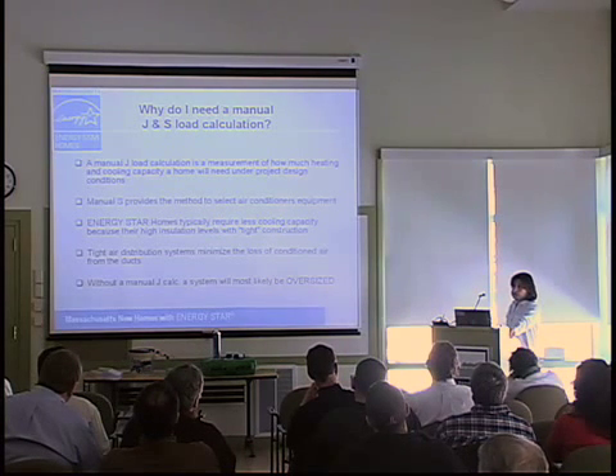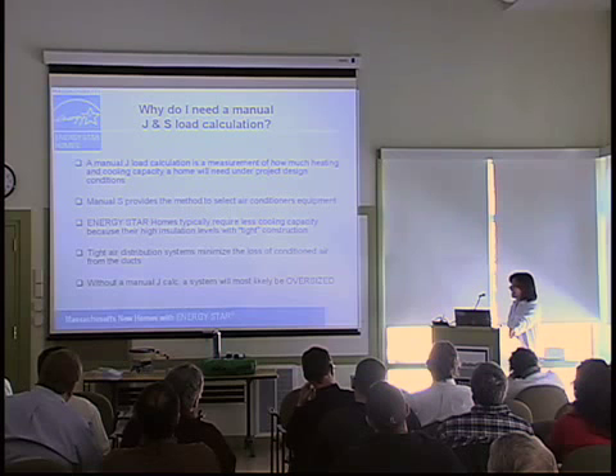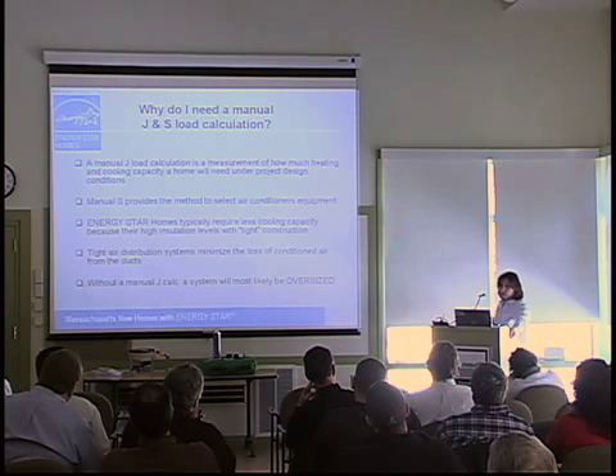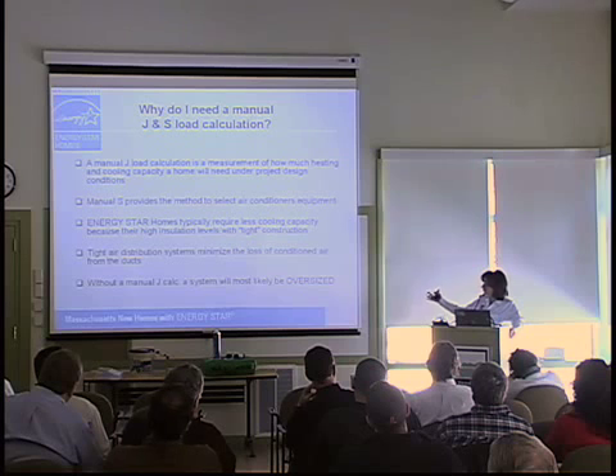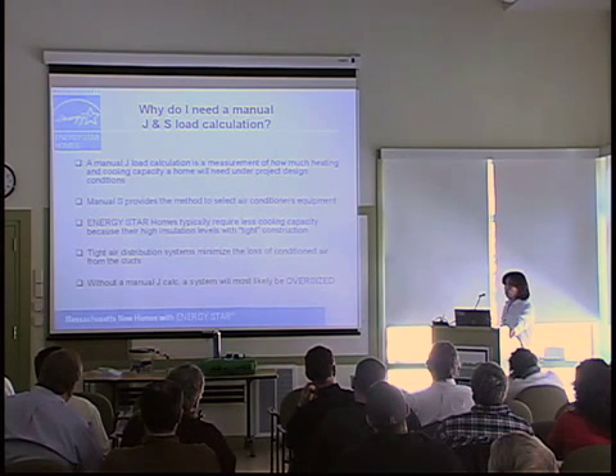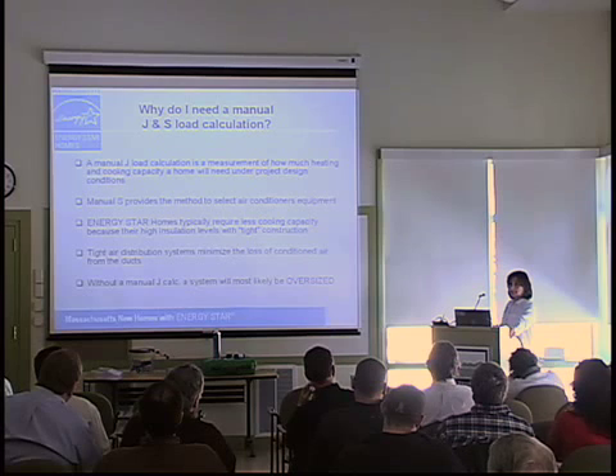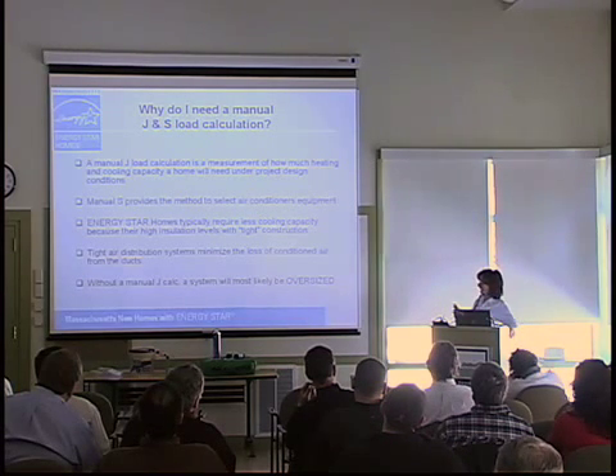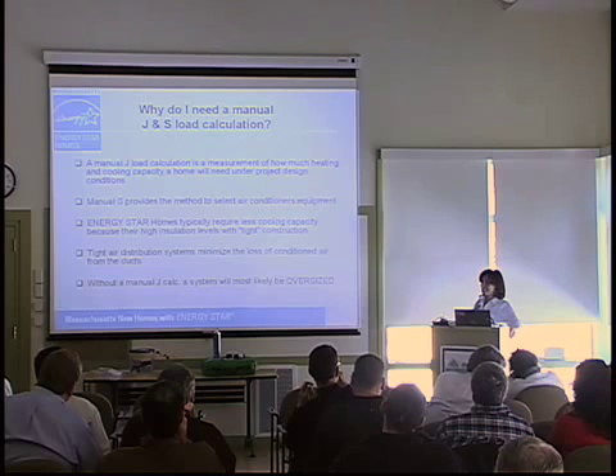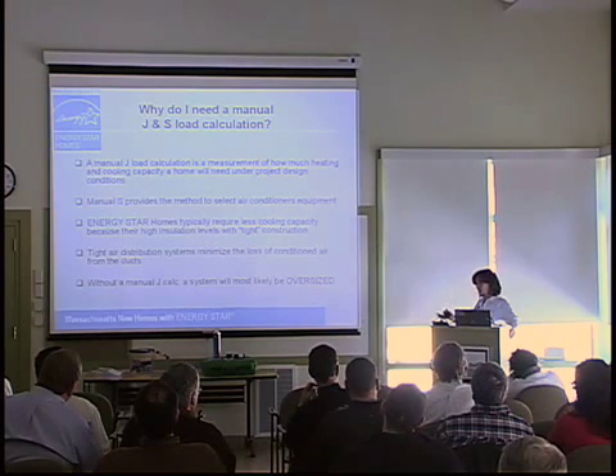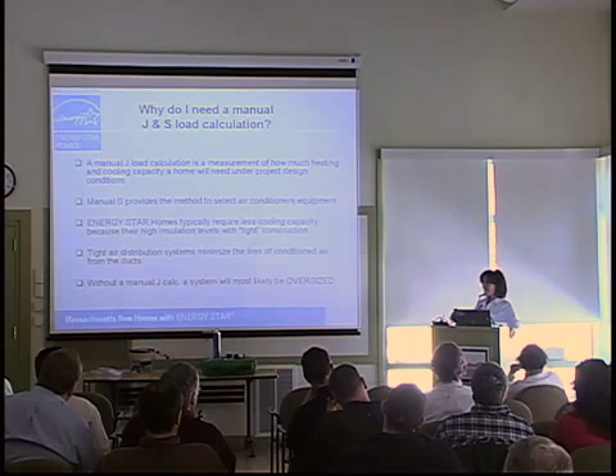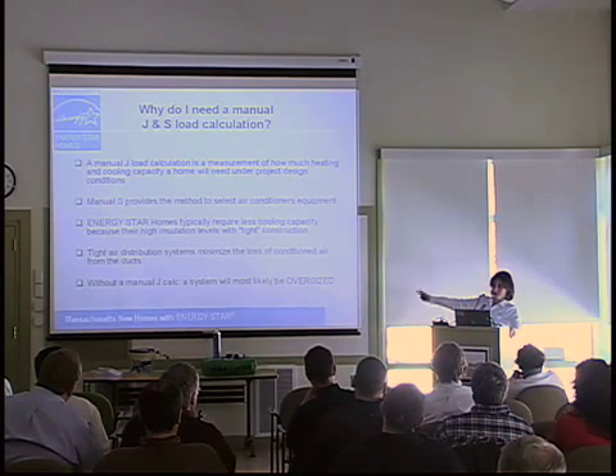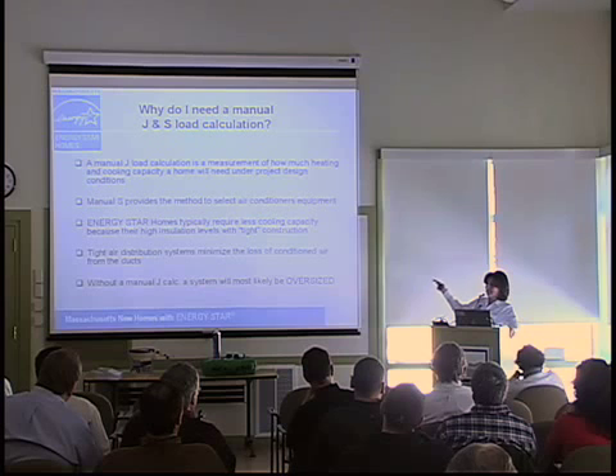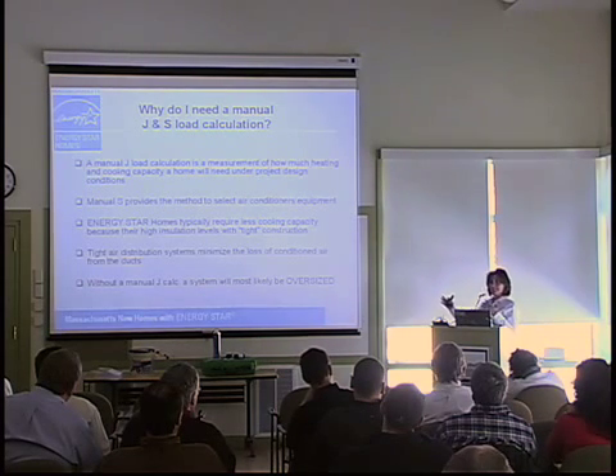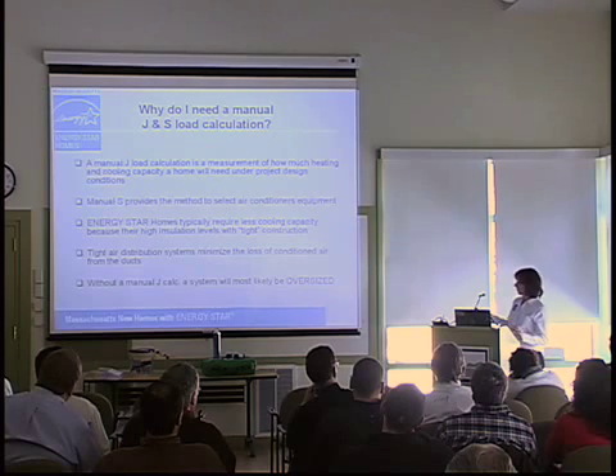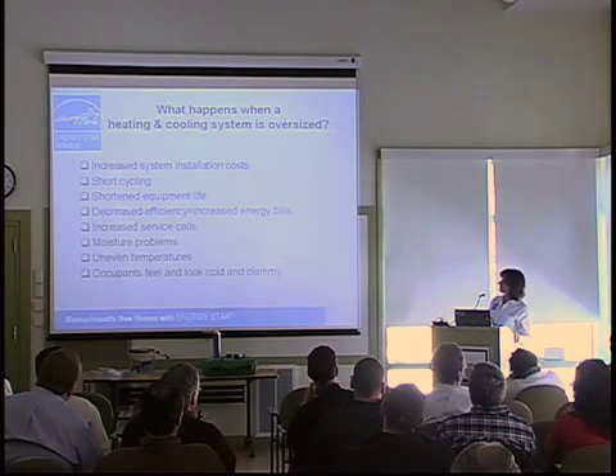So without a Manual J load calculation, if somebody is, again, sizing a system by rule of thumb, without your plans, without your Manual J, then the system will most likely be oversized. Oversizing is a comfort level that has been going on for many, many years. It's more often that systems are oversized than undersized. However, the complaints that you could get from an oversized system are often what people or contractors perceive as undersized systems. So it's kind of interesting how that happens.